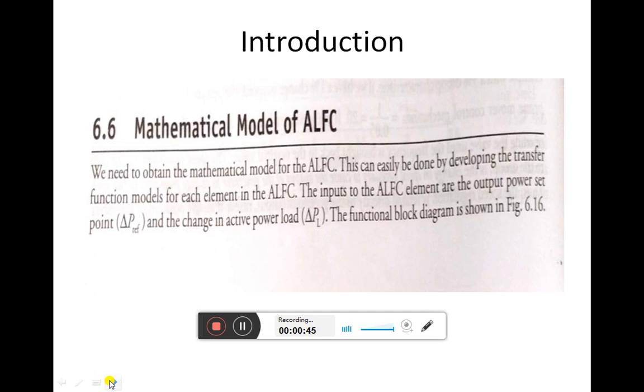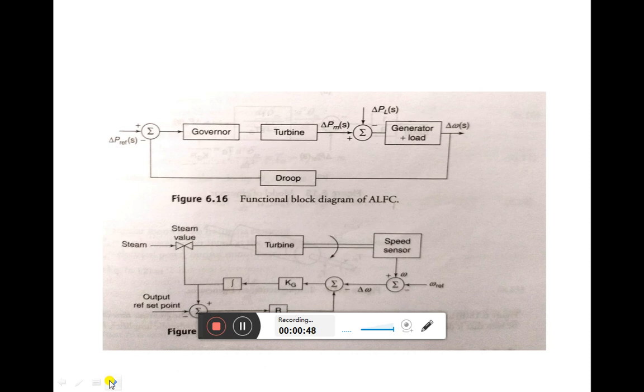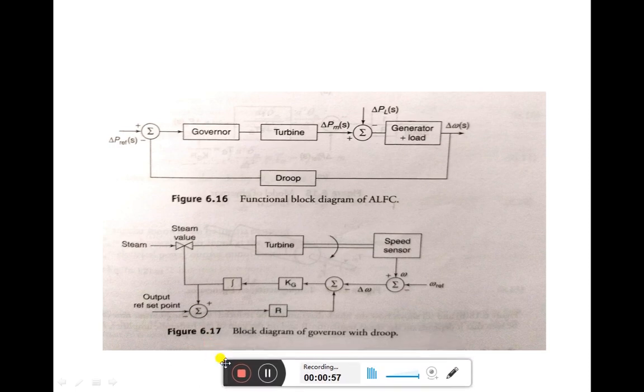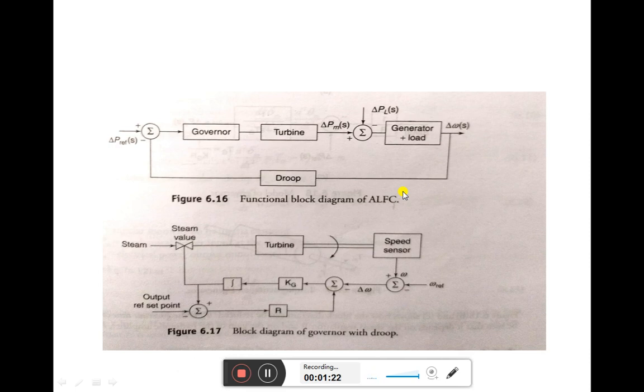The functional block diagram of automatic load frequency control can be seen here. The important blocks in the ALFC loop are the governor, turbine, and generator plus load. The function of the automatic load frequency control loop is to maintain the frequency at the nominal value, and if there is any deviation in the frequency, to adjust the input such that this frequency deviation becomes zero.